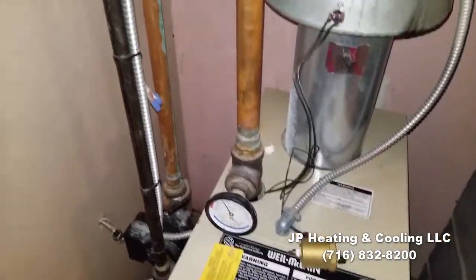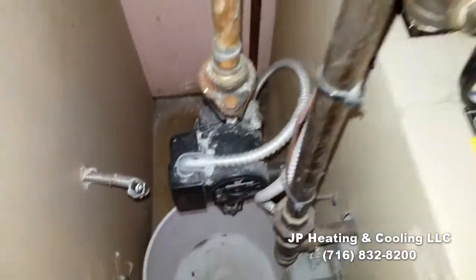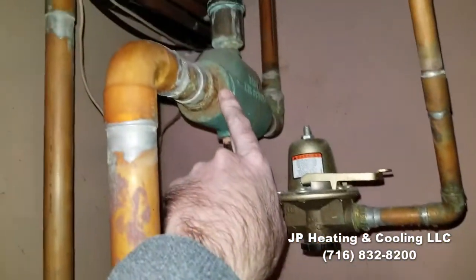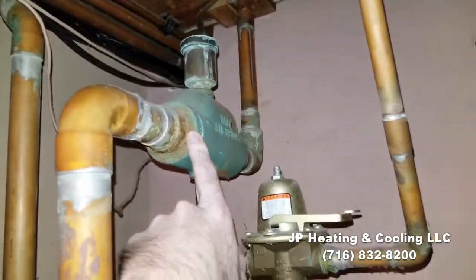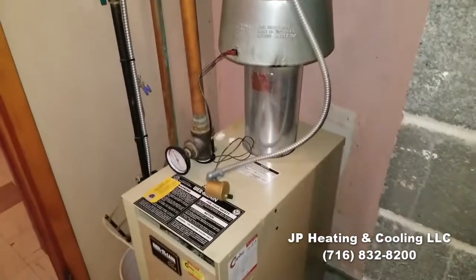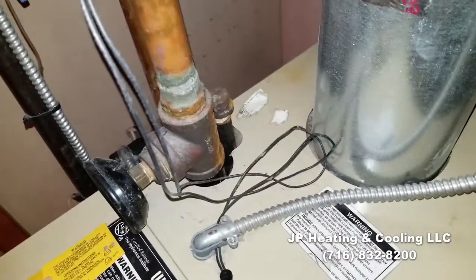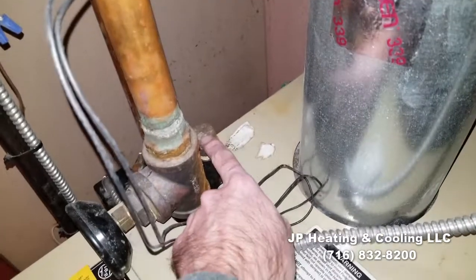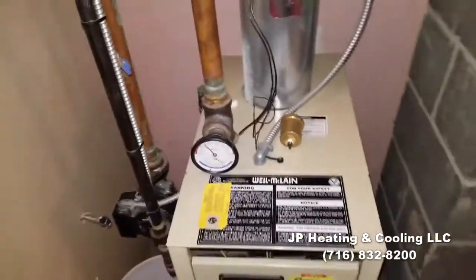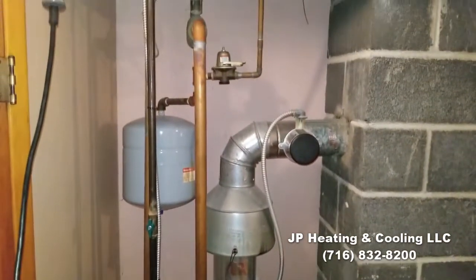We're going to get this pump off the return, replace the expansion tank and fill, put a micro bubble eliminator and get rid of the air scoop, and put a low water cutoff on it. They also capped the internal air scoop in the block for some reason, so we're going to put an air vent on that and put a power purge setup on it.